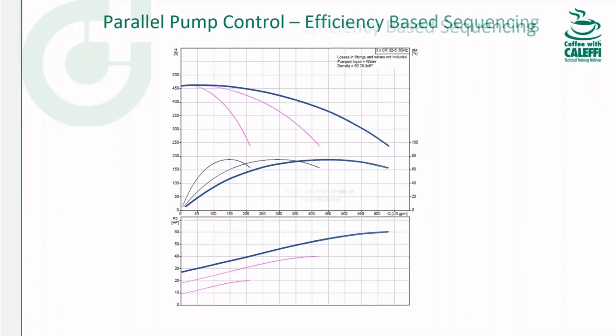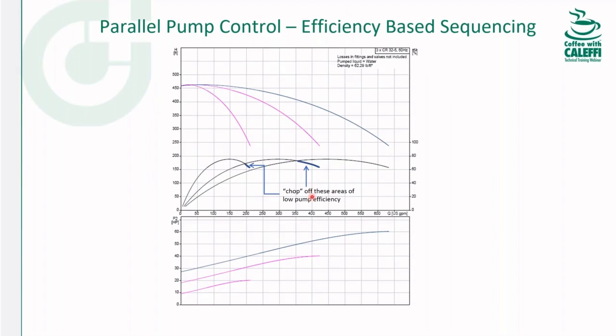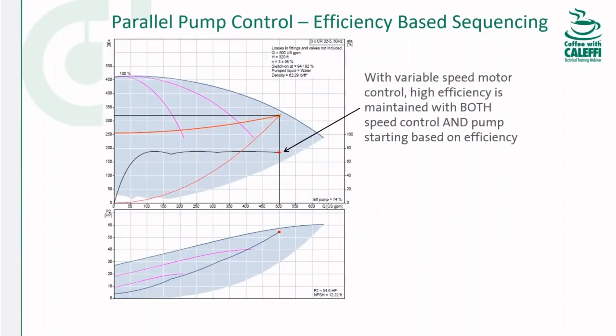But if we look at 350 GPM, you see that with two pumps the efficiency starts to drop, but with three pumps it's higher. So what we want to do here is chop off those trailing edges, and a pump controller that knows where the pumps are operating on the curve can do this automatically and instantaneously. In Grundfos's online selection program, this would be a triplex selection, and the bolded red line would be our control curve.